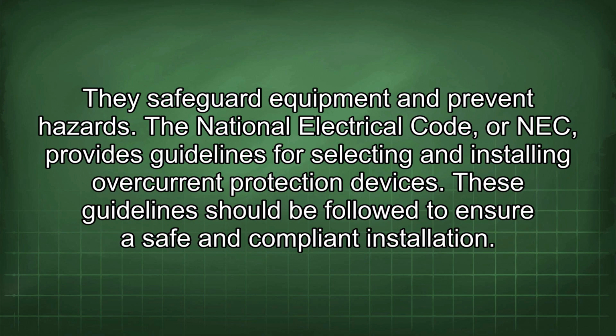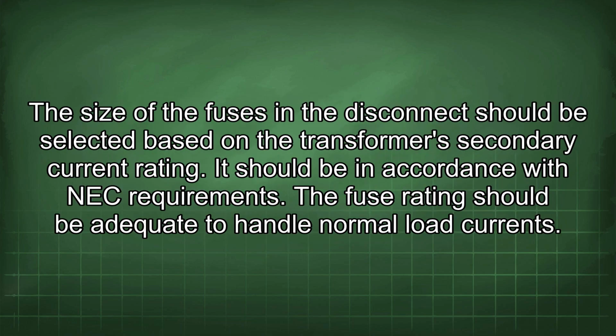The National Electrical Code, or NEC, provides guidelines for selecting and installing overcurrent protection devices. These guidelines should be followed to ensure a safe and compliant installation. The size of the fuses in the disconnect should be selected based on the transformer's secondary current rating. It should be in accordance with NEC requirements.